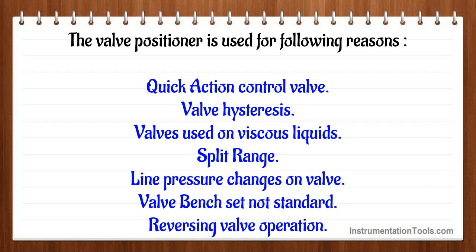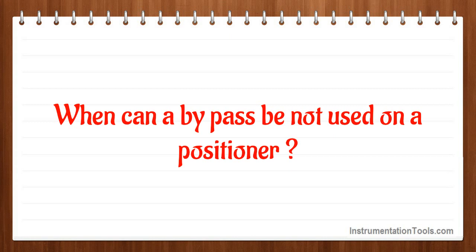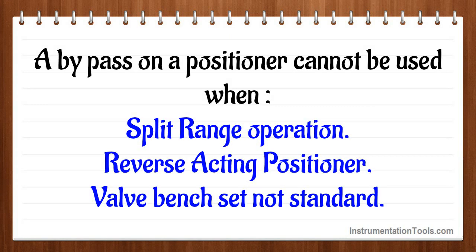When can a bypass not be used on a positioner? A bypass on a positioner cannot be used when: split range operation, reverse acting positioner, or valve bench set not standard.